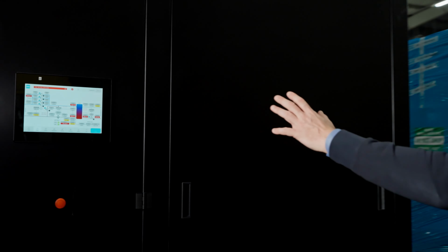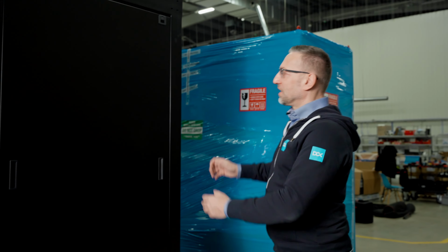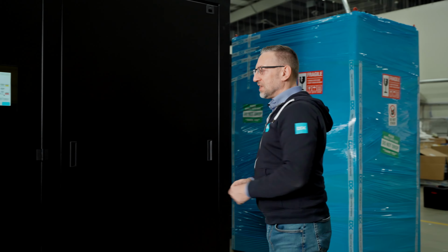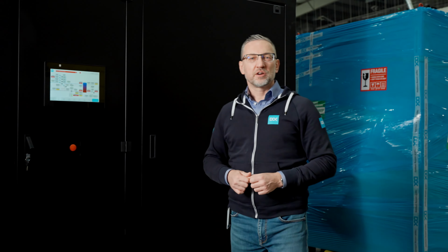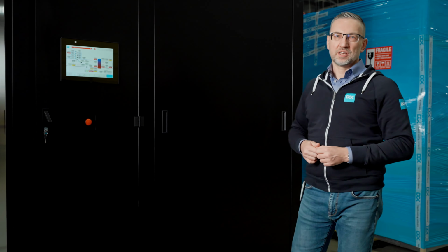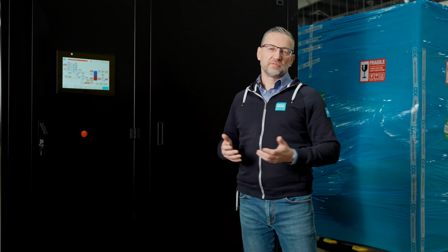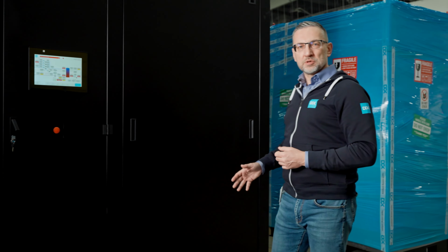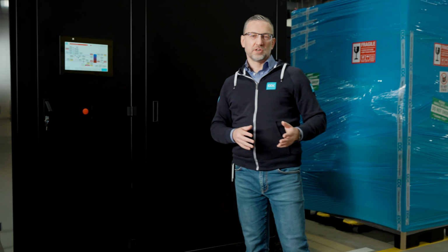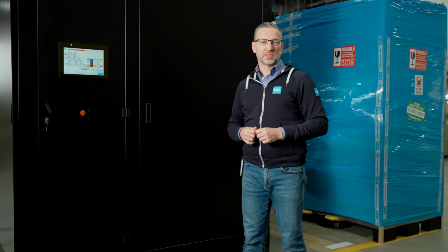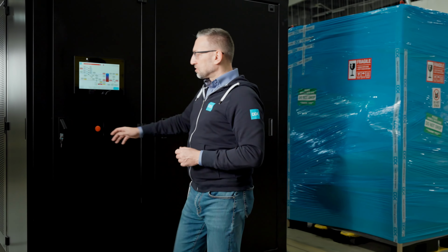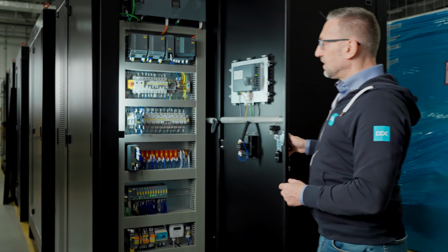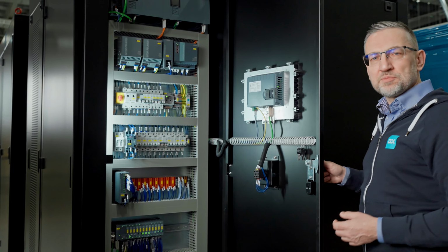So that's the C-frame, and in the C-frame we have the pipe assemblies hidden behind that panel. These are vertical pipes, so we can connect flexibly from the top or from the bottom for both primary loop and secondary loop, so TCS side and facility water system side. That's the control panel. It's pretty comprehensive, pretty large.